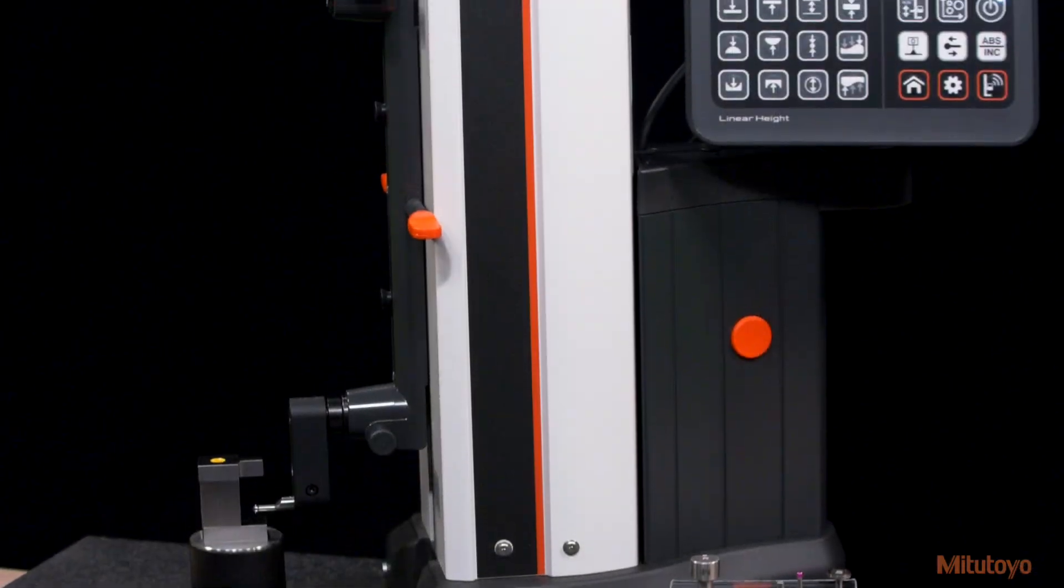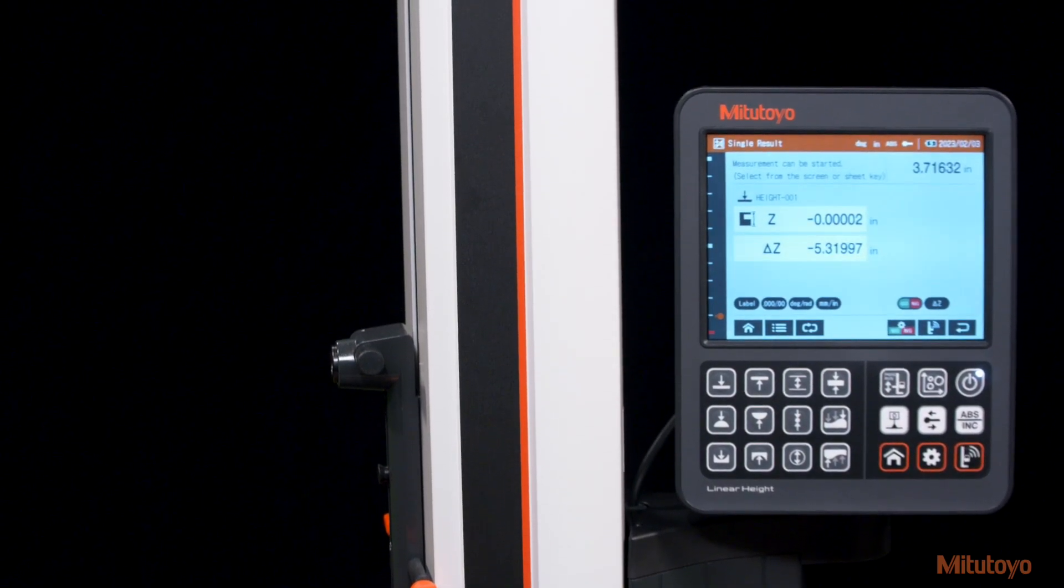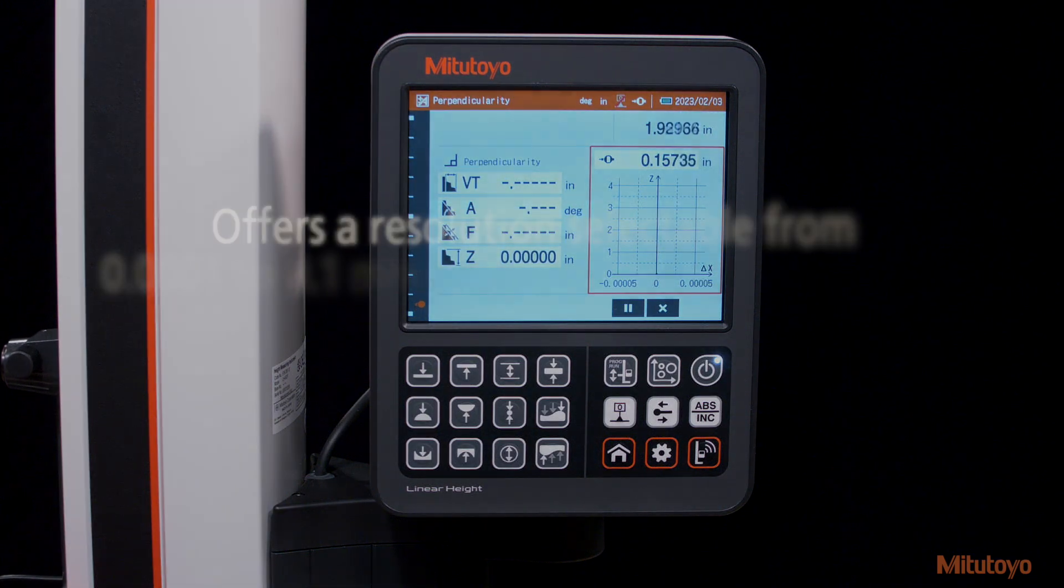Let's take a quick look at what makes the LH600F the most accurate height gauge in precision metrology. The heart of the LH600F precision lies in its photoelectric incremental encoder, allowing for ultra-fine measurement increments even in shop floor applications.